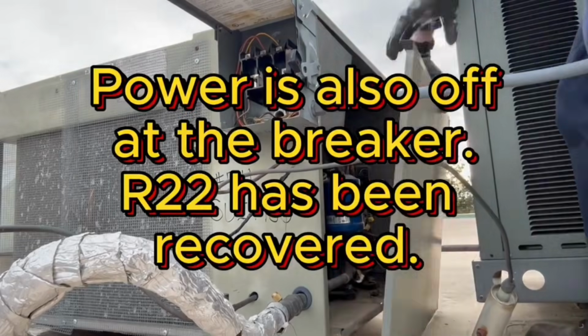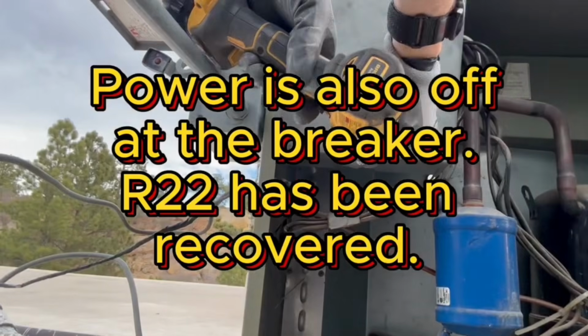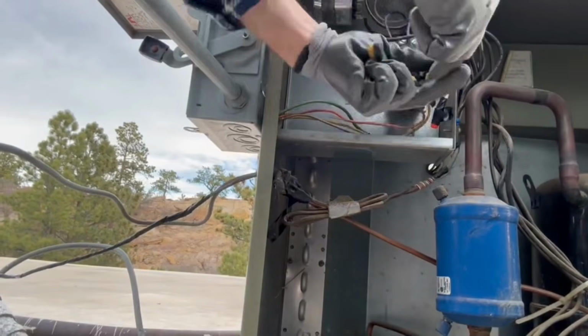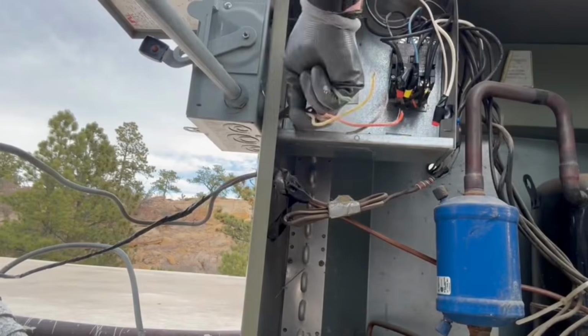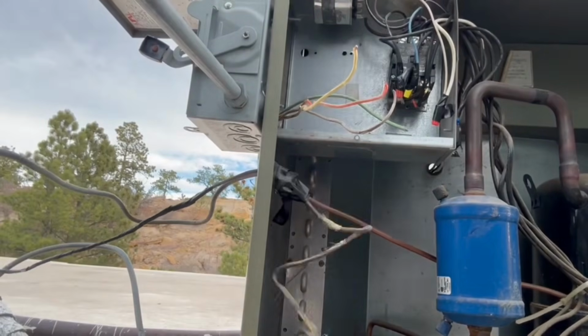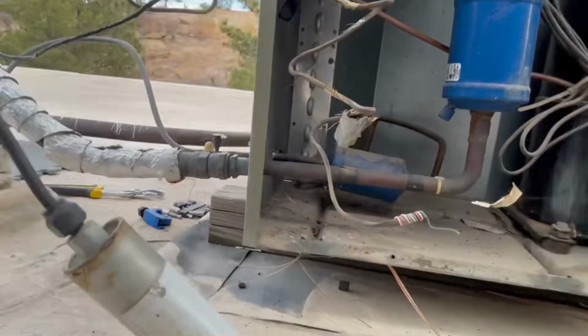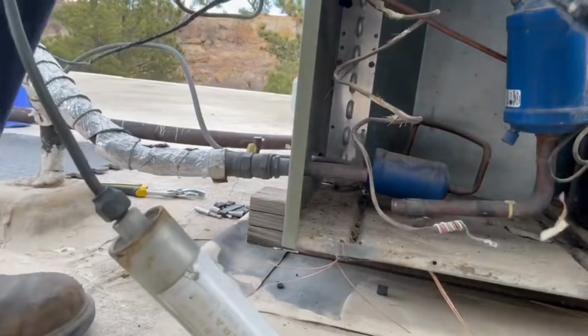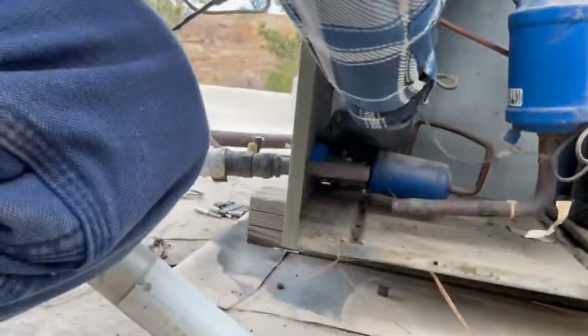I'm going to turn the power off to the unit, take the side panels off, disconnect our 240-volt three-phase wires coming into the unit, as well as our thermostat wires. We're going to reuse the disconnect switch, and we're going to reuse the thermostat wires and the line set. And so, since I've recovered the refrigerant out of the system, obviously I can disconnect our line set as well.